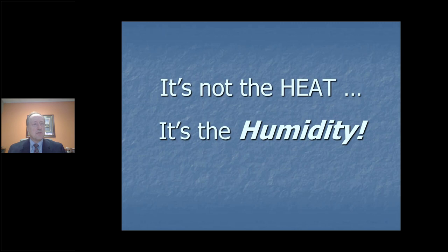Let me try to address some of those, and if I don't get all the questions, come back to me. How much does moisture affect the heat transfer capability of a cooling coil? Tremendously. If you sell equipment, for example, or if you have software that shows cooling coil capacity, if you were to show the entering air condition to be much drier, the dew point either at or not too high above the apparatus dew point of those coils, you'll see that it can very easily take care of the sensible load.